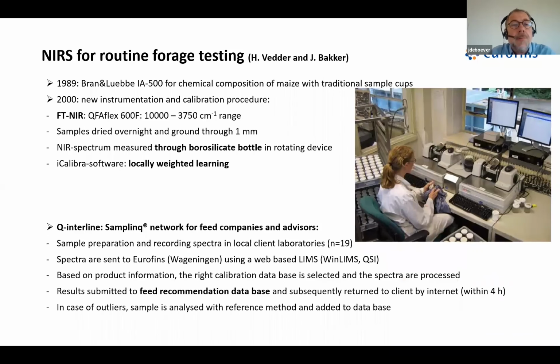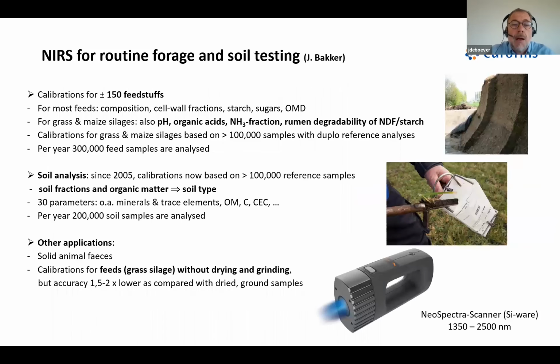Another application is in a big forage testing lab, where they have a Fourier transform NIR instrument, which enables to scan the samples in the bottle, and they develop calibrations by locally weighted learning. This instrument is in Wageningen, at Eurofins, and is connected in a network with different clients, for the moment 19 laboratories, which send their spectra to the central lab, which then gives a recommendation within 4 hours to the clients. Eurofins is also used for soil analysis and now also for grass silages without drying and grinding by using a handheld scanner.